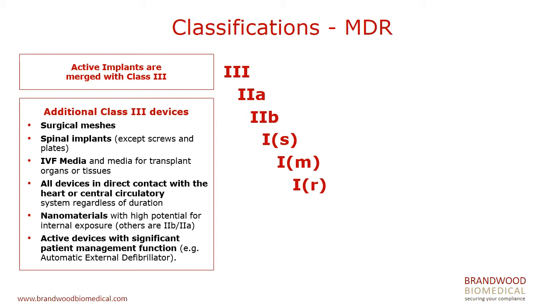Now IVF media and other media for transplant organs or tissues are all class 3 devices. Anything in contact with the heart or the central circulatory system now becomes class 3, regardless of the duration of contact. In the old regulations, short-term contact had lower classifications. That's no longer the case.